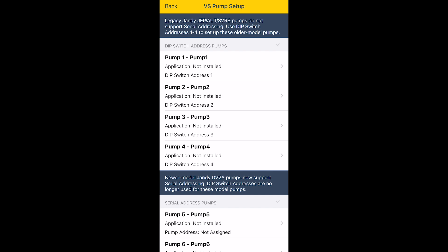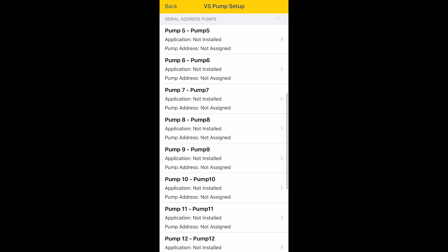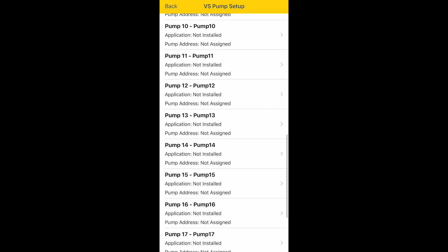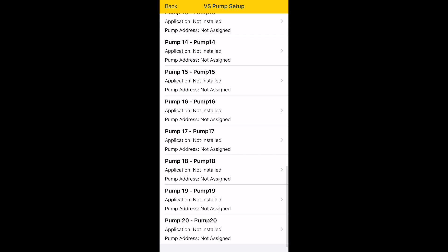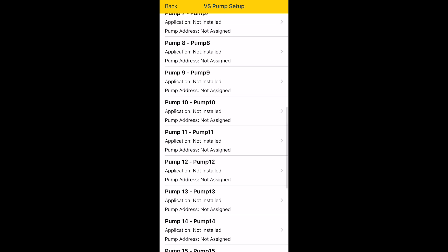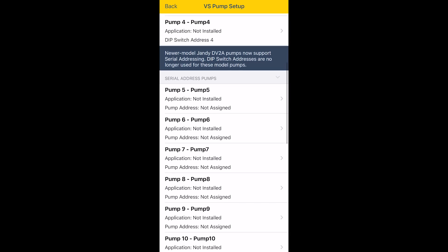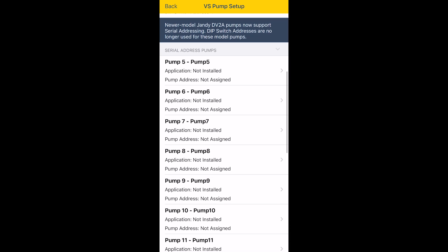So we're going to click on that. And then you will see that if you have legacy pumps at this point that do not have serialized addresses, you can now set them up in app mode. You don't have to go into web mode. And you would assign your pumps here the same way that you would in web mode. So your pumps would have a dip switch setting of address one, two, three, four. Now, if you come down here to the serialized address pumps, you'll notice we have a lot more options. So we can actually have pumps five through 20 assigned individually as variable speed pumps.